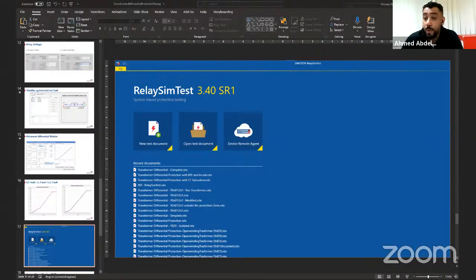This is an OCC file from Omicron Control Center, where you can do everything related to the protection. Here you can see it looks like that. Here we have the OCC file, and in the OCC file, it's a very easy way. It's like a container, and in the container we have everything available there. So what you need to do is just go to the relay software, export the setting from the relay software, import it here in our Test Universe, and the Test Universe and the OCC file will calculate the complete characteristic of everything. And finally, you will go here, for example, for the diff configuration.